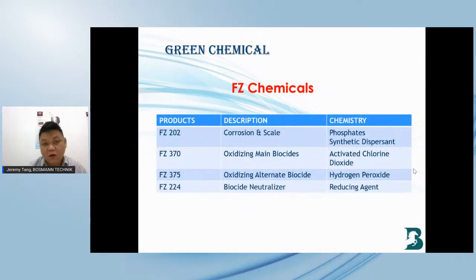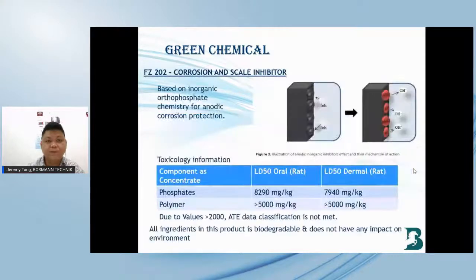For the green chemical, we divide it into four units. The first is phosphate and synthetic dispersant, a corrosion and scale inhibitor. The second is activated chlorine dioxide, the main biocide for cooling water. The third is hydrogen peroxide, the alternate biocide for cooling water. The fourth is a reducing agent to neutralize the chlorine dioxide before discharge.